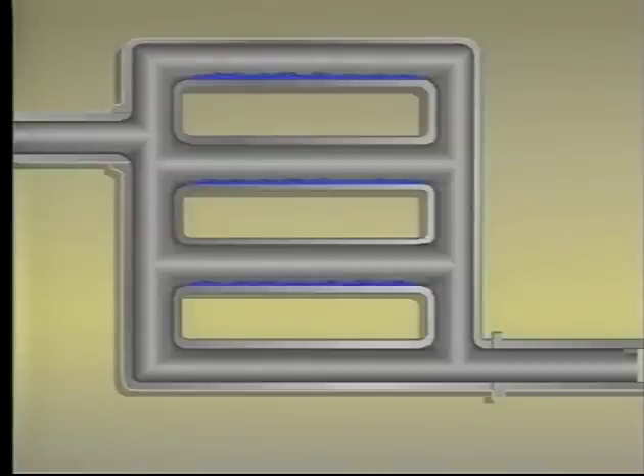Thermal shock can also occur easily in steam coils if they are constructed as shown here. Since the steam is directed toward the center tube first, it can reach the return header before the top and bottom tubes are filled.